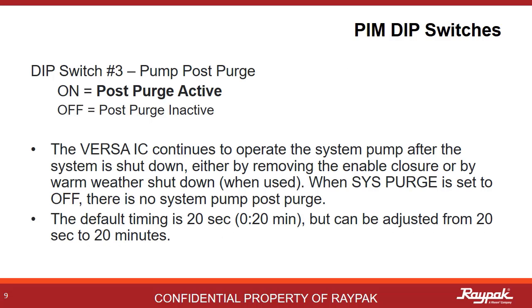Dip switch number three controls the post purge option. Post purge allows the pumps and the cold water protection systems to run for a bit after the burner shuts off. This extra 20 seconds of pump run time gets the residual heat out of the combustion area so you do not trip on a high limit accidentally. The default time is just 20 seconds, but it can be adjusted from 20 seconds to 20 minutes.